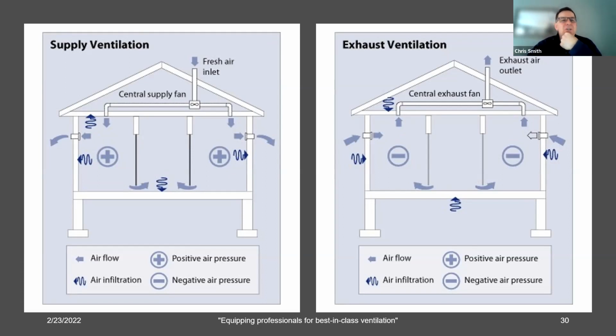Now, with supply ventilation and exhaust ventilation, you usually have a pretty easy installation, one or more fans, and easy duct systems, usually pretty easy. And you don't have to think about much more than that. But again, you're mostly relying on infiltration or exfiltration. With supply ventilation, you can control where you get your supply air. But with exhaust ventilation, your supply air, again, is still coming through the sort of nasty cracks of the building. So you're not controlling air quality all that well. And you're basically losing energy.